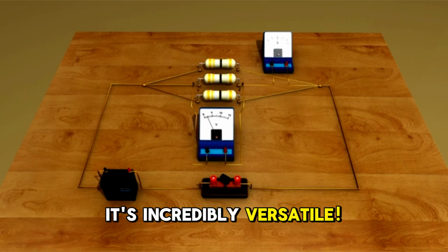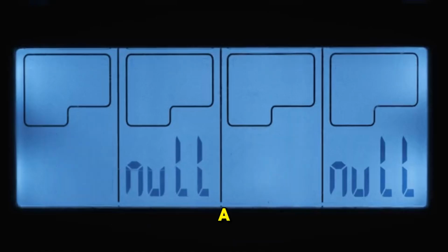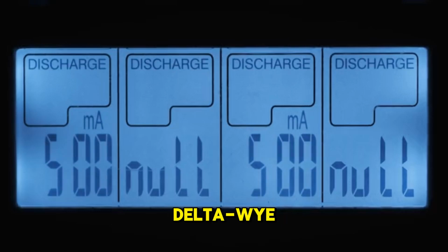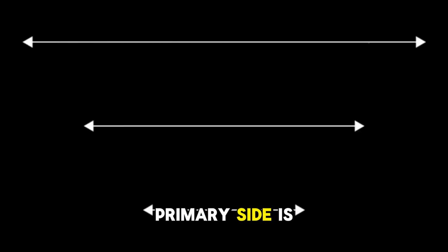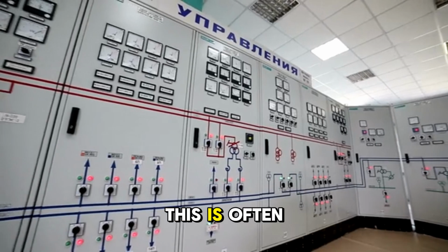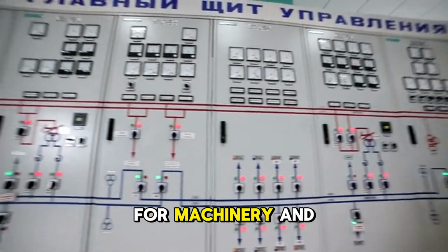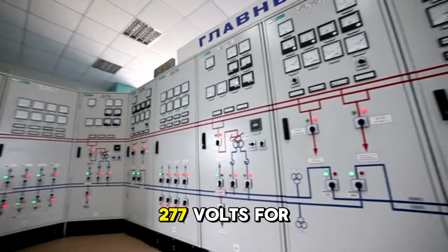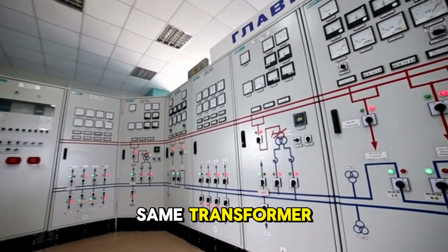It's incredibly versatile. A very common setup you'll see on a transformer nameplate is delta-Y. This means the high voltage primary side is connected in a delta configuration, and the lower voltage secondary side is connected in a Y. This is often used to get 480 volts for machinery and 277 volts for lighting from the same transformer.